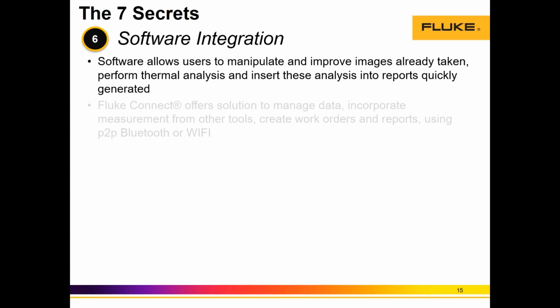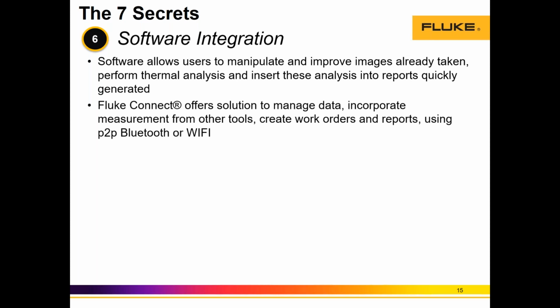There's only one thing that we cannot change through software, and I think I mentioned this before, which is the focus. So it's critical that we have a good focus, and I think we mentioned this in secrets 2 and 3. And within the software capability also, what better than a clouded solution that will allow us to manage data, and in this case, images, and incorporate these infrared images with other measurements with different assets or different tools from Fluke or other families, right? Incorporate a thermal image of a motor with a power quality analysis done with a multimeter, with a power and a clamp meter, or with a full power quality analyzer tool.